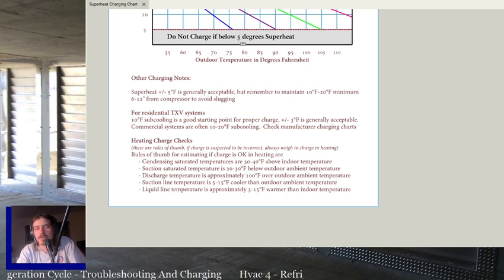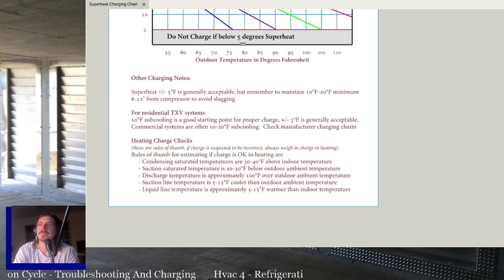Scroll compressors are a little more able to deal with a little bit of liquid getting in there and stuff like that. Most compressor designs, even if you've got zero superheat to the compressor itself, by the time it goes across the motor and everything in that compressor, you usually have something. But don't let it get too low, and obviously too high, you're just going to burn it up. So you want to keep superheat as close as possible to where it should be, but don't charge it.